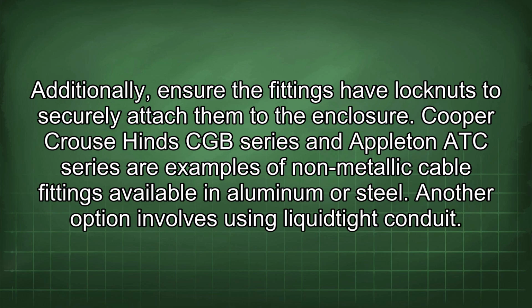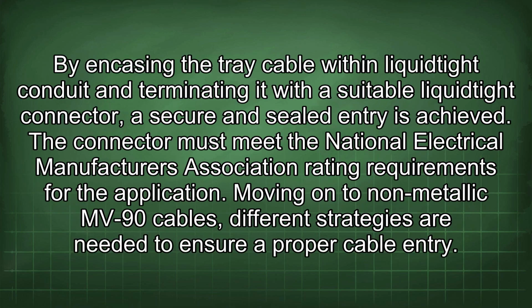Another option involves using liquid-tight conduit. By encasing the tray cable within liquid-tight conduit and terminating it with a suitable liquid-tight connector, a secure and sealed entry is achieved. The connector must meet the National Electrical Manufacturers Association rating requirements for the application.